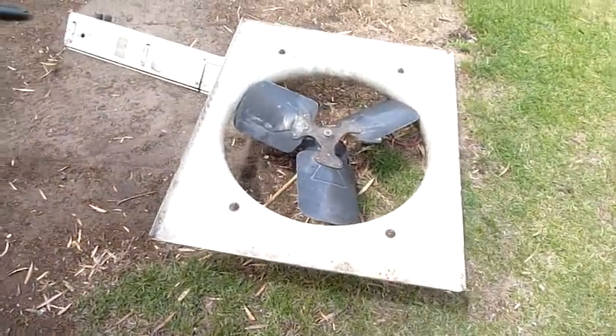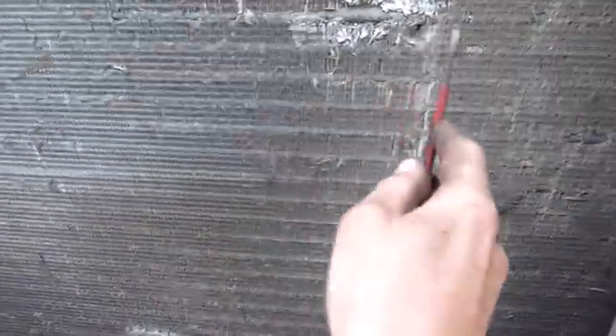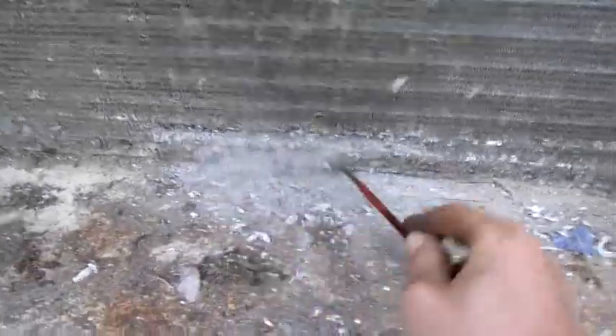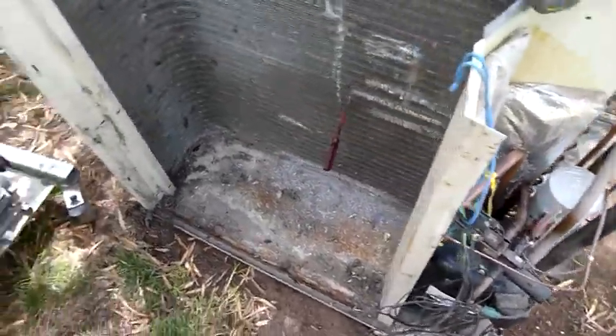Okay, I've got the fan out. Decent sized cowling on it. It's about 1 metre by 800 millimetres. And as you can see, the coil looks okay from a distance, but when you get up close, it's almost gone. That's why it wasn't working properly. It's dead. Anyway, I'll get the sawzall out and cut all that off and get the compressor out, and that should do it. The screw still in that one.